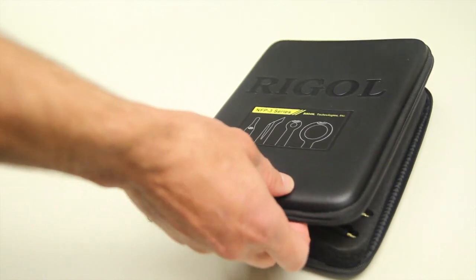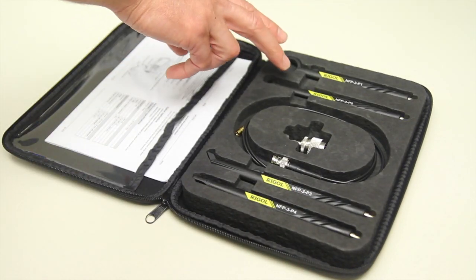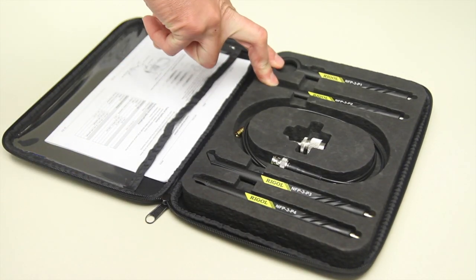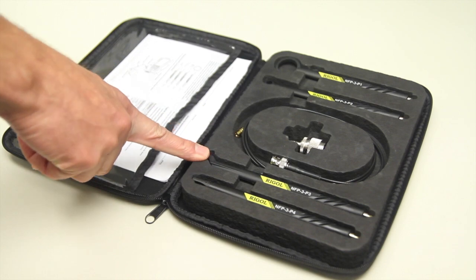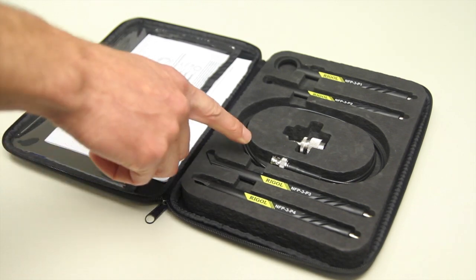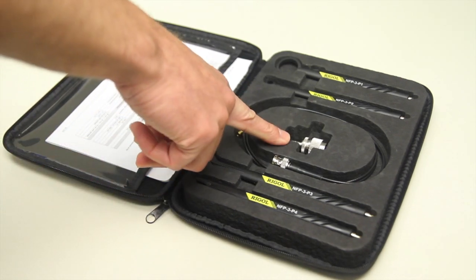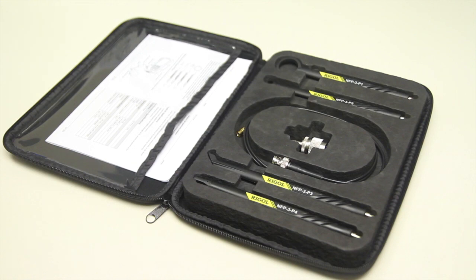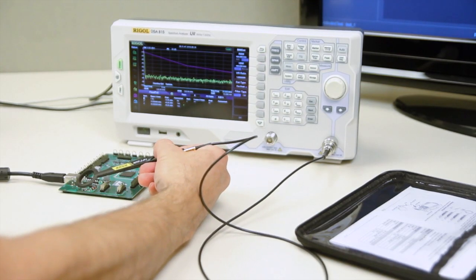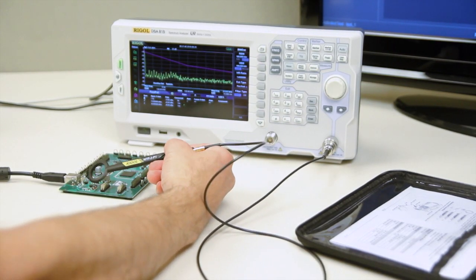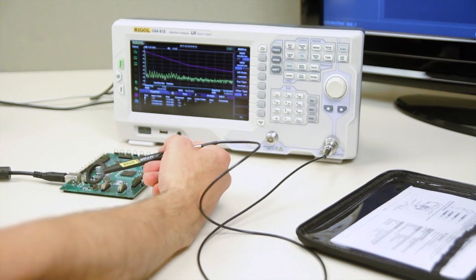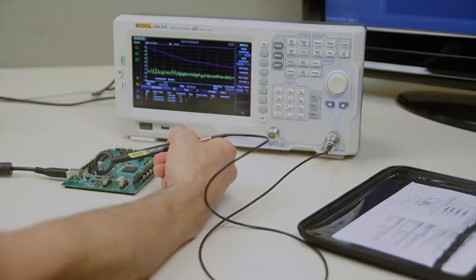The kit comes with a handy carrying case, two near-field probe loops, one line probe and one point probe, as well as cable and adapter for connection to your Spectrum Analyzer input. The main use for these probes would be troubleshooting EMI sources on boards and enclosures.